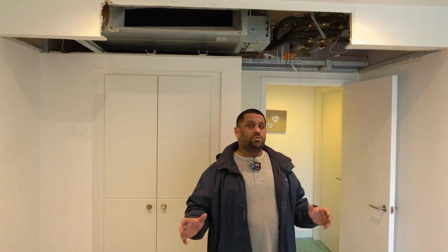So what's a chilled water fan coil unit? Above my head, it looks like a conventional air conditioning unit, but it doesn't use refrigerant. It actually uses chilled water provided by a central plant in a building, and it distributes the cooling throughout the rooms. There are a set of actuator valves which control the flow of the water and the cooling requirements to the unit, and it's all controlled by a BMS and thermostat to make sure it all hums along energy efficient.